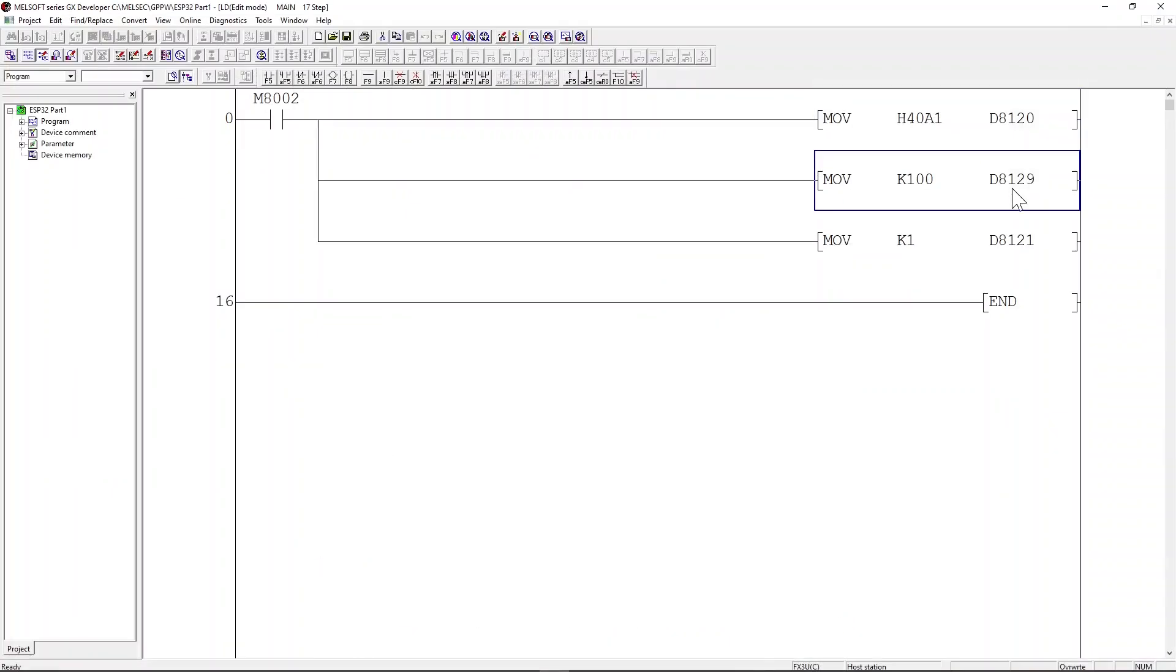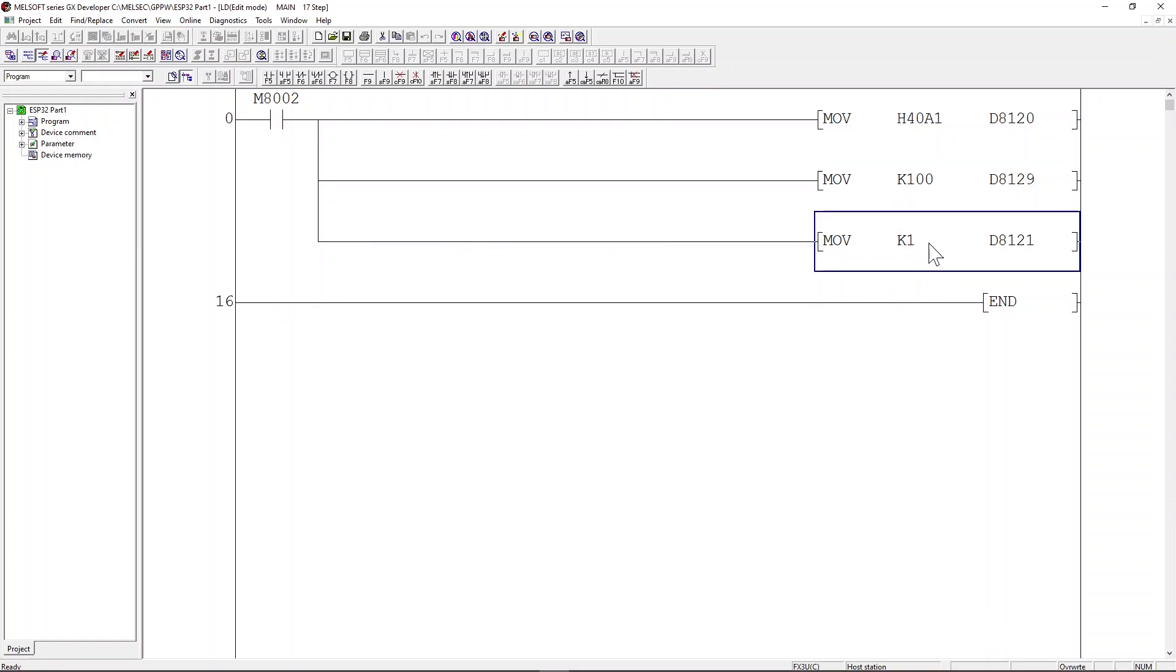The next register that we need to set is D8129, which is a special register for communication timeout. In this example, we set the communication timeout to be 100 milliseconds. The next register D8121 is a special register for the PLC station number. In this case, we set the station number to 1.